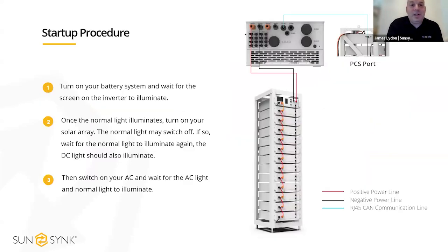Okay, so the startup procedure. This is showing the 50, but this applies to all of our hybrid inverters. Our recommendation as a manufacturer is, when you've got a hybrid system installed and you've got your PV connected, your grid connected, and your batteries connected, we always recommend you isolate the PV, isolate the grid, and just get the system working with the batteries.